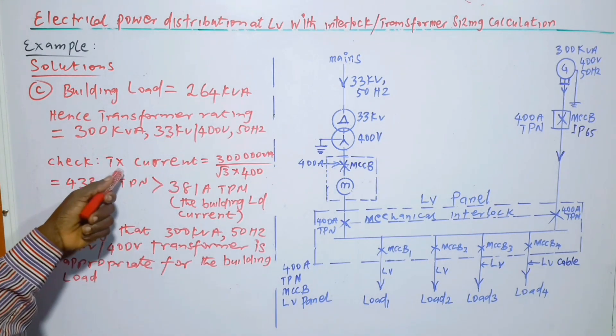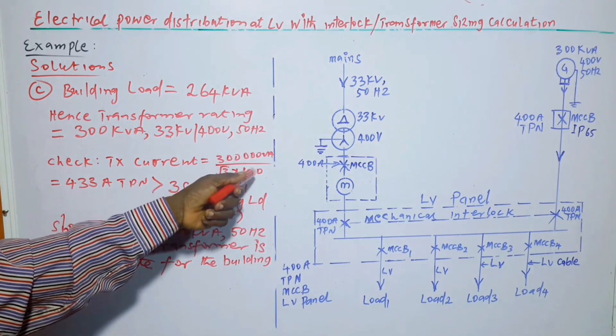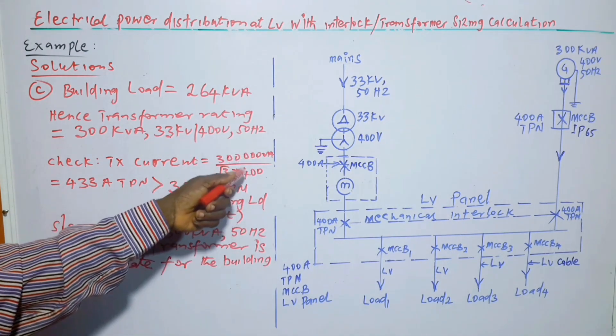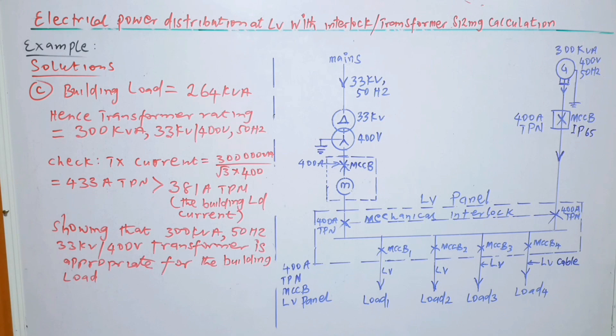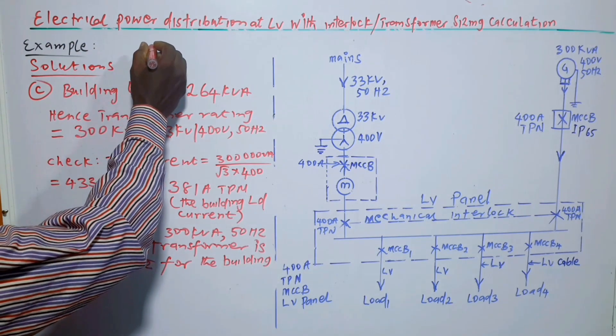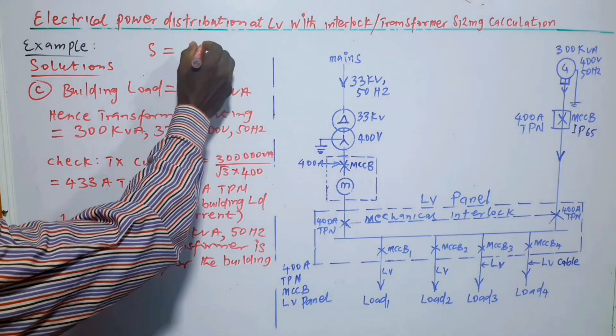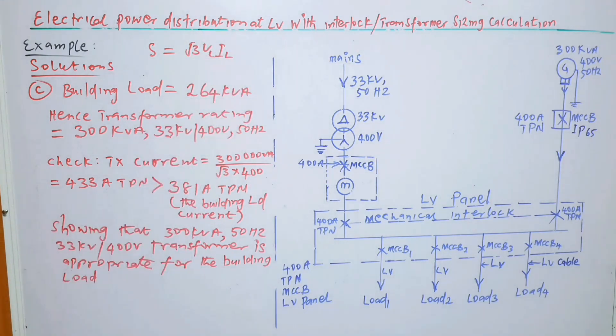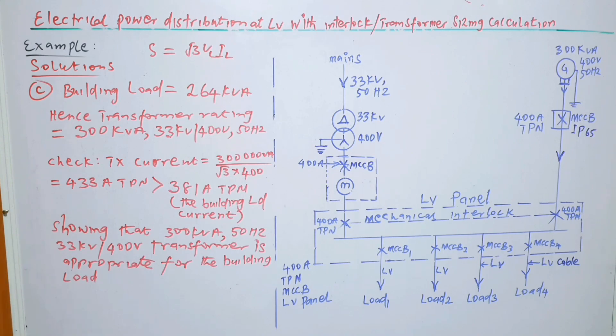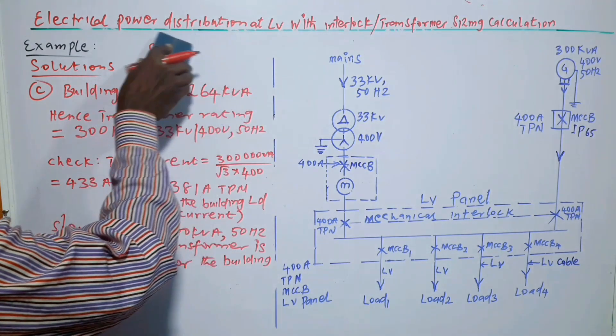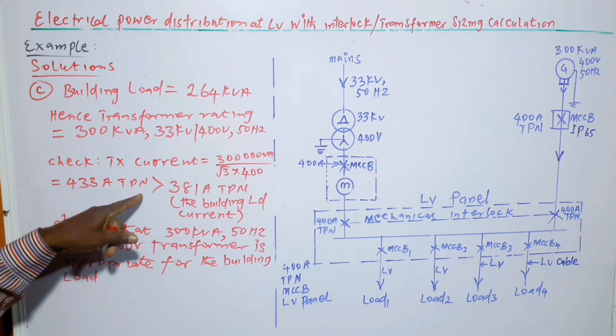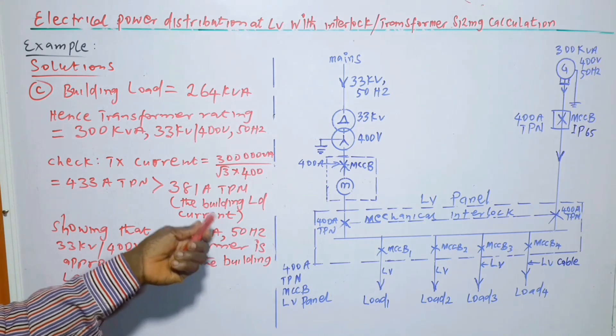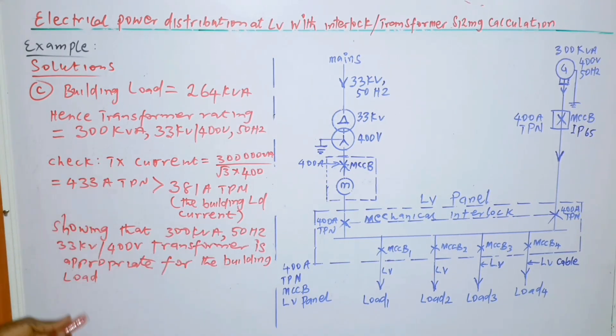Then we can check, the transformer current is 300 kVA or 300,000 VA divided by root 3 times 400. From the apparent power formula, S is equal to root 3 V line I line. So from there, we can calculate the current. If it is correctly calculated, the answer is 433 ampere triple phase with neutral, which is greater than the load current calculated in the B part.